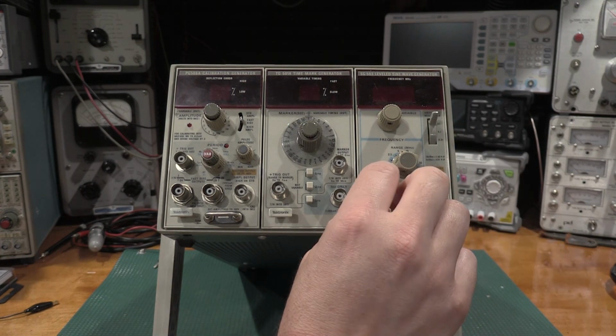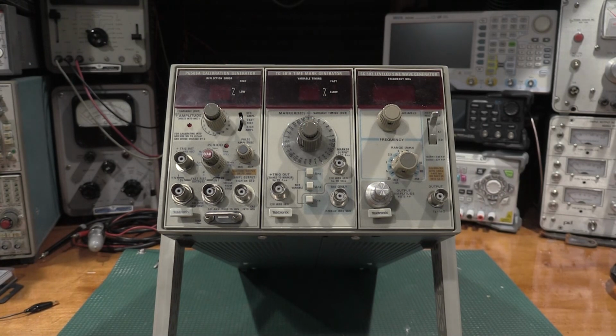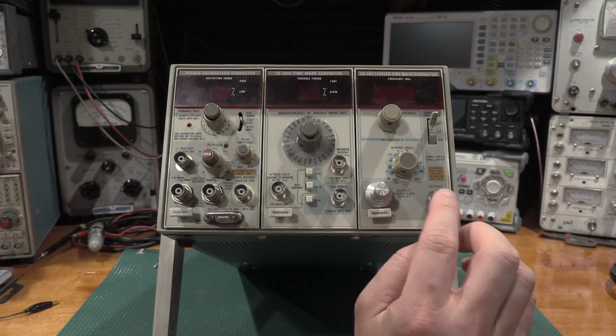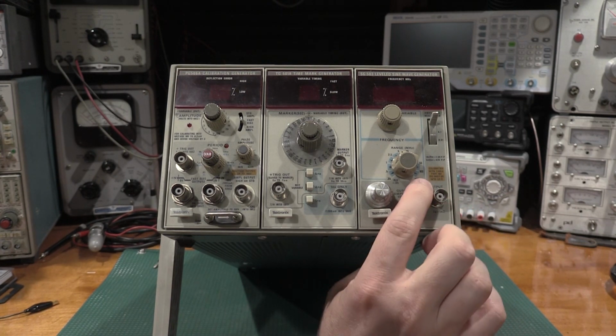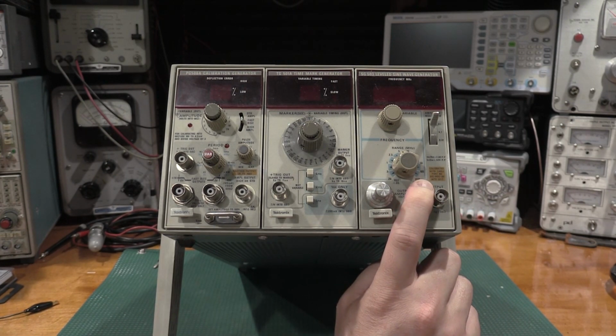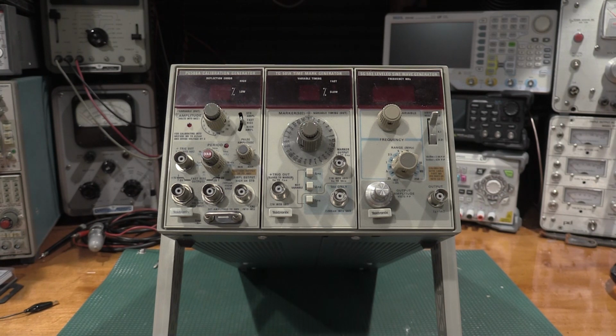And then we have a dial of voltage with a 10-turn pot. But if you read here, it says calibrated with cable, and it gives you a part number for the cable. It's a very accurate 50 ohm cable, and it's not hard to find, but when you do find it, it tends to be on the more expensive side. I have one, but I don't use it with mine very often for doing calibrations because the error it puts into the system is not high.